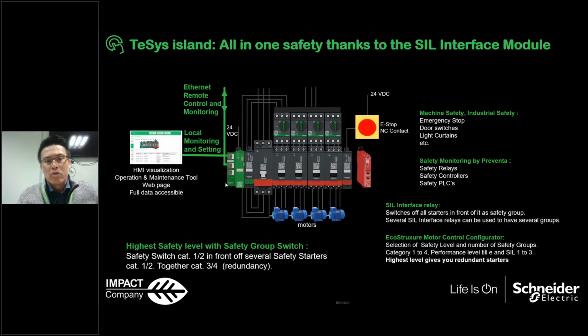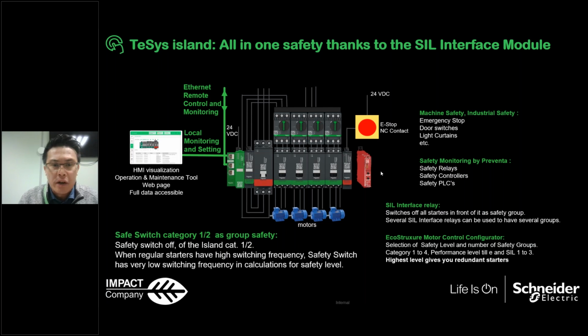And also, we provide the safety circuit or the starters for the system. We also have a reference for the safety starters if you need to achieve SIL level 1, and safety category 1, 2, 3 or 4 for the redundancy in the safety circuit. We also have a safety interface module to equip with the safety starters together for the safety level, for the safety group switch, and also for the e-stop and the safety relay. So it is all ready for the safety circuit as well. You can achieve different categories with different configurations, with a standard starter or a safety starter.